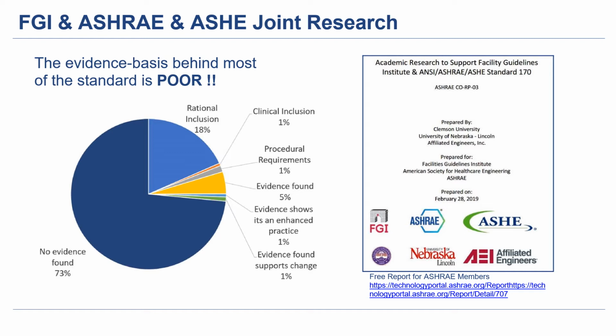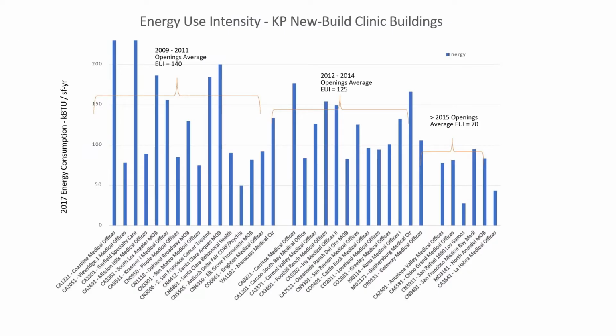This is a long way of saying that Kaiser Permanente has not adopted those air change rules in our clinics. We don't adopt ASHRAE Standard 170 anywhere we're not required to by law, and that's fairly fundamental to this project. This building is a clinic with a variable volume system and a return plenum. If we followed the air change rules, the performance we're talking about here just wouldn't be possible.